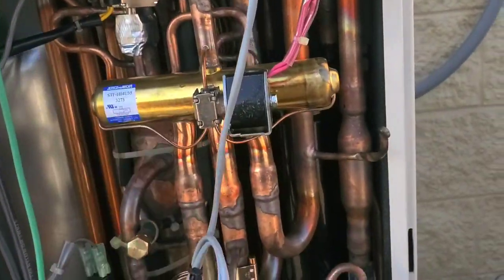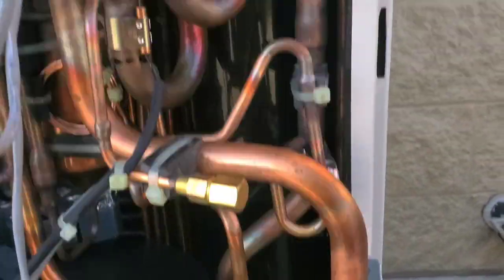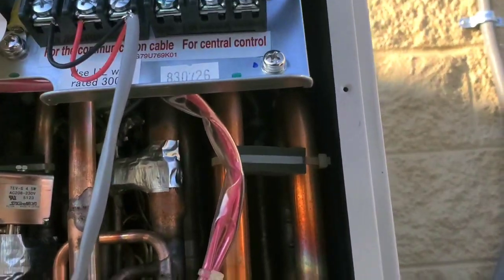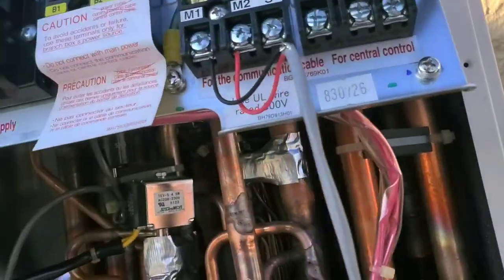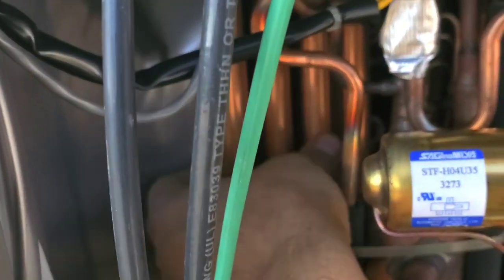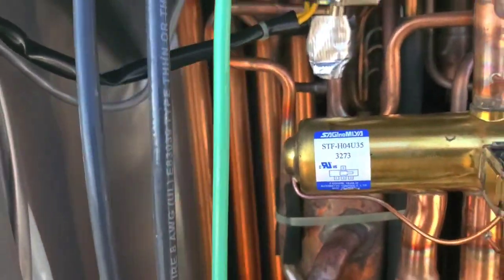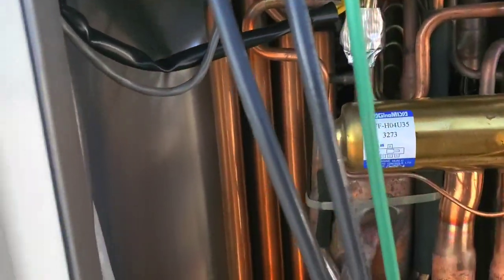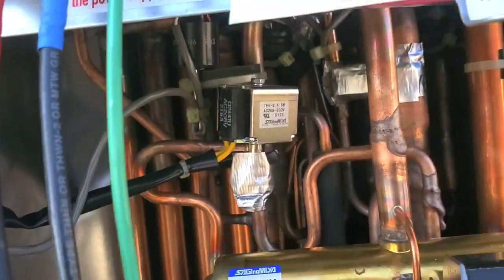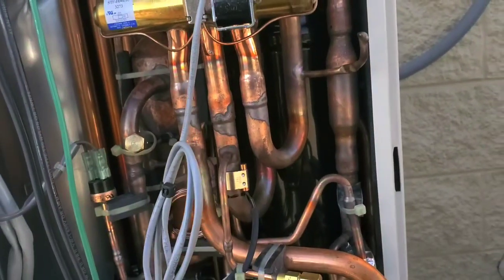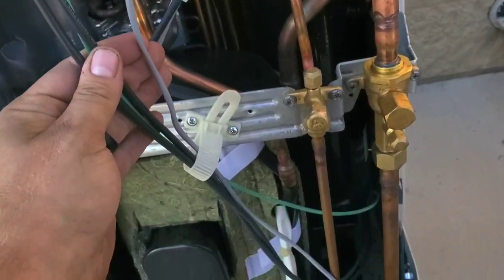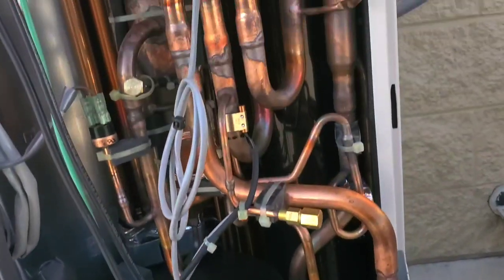We got our reversing valve. We got a gigantic receiver all the way from top to bottom. Here's 4 heat exchangers piped in like some kind of series parallel array. A solenoid valve, lots and lots of components. Everything you could possibly put in an AC unit except a filter dryer.